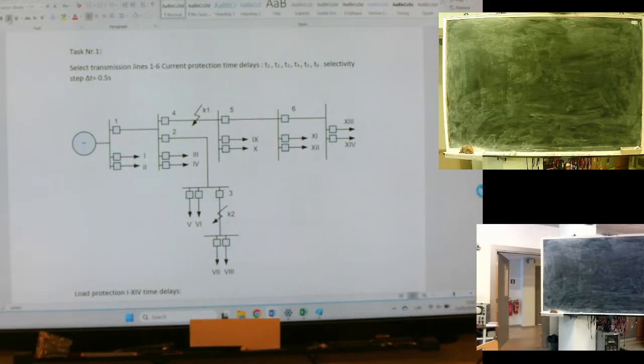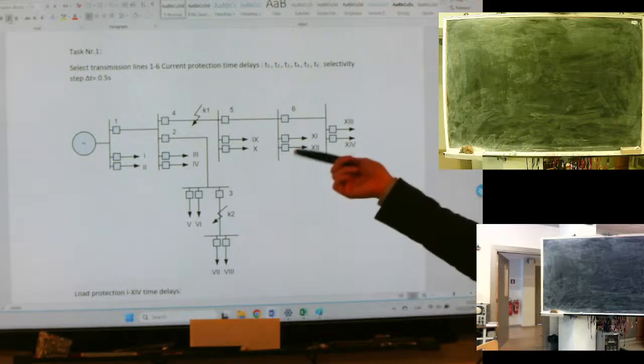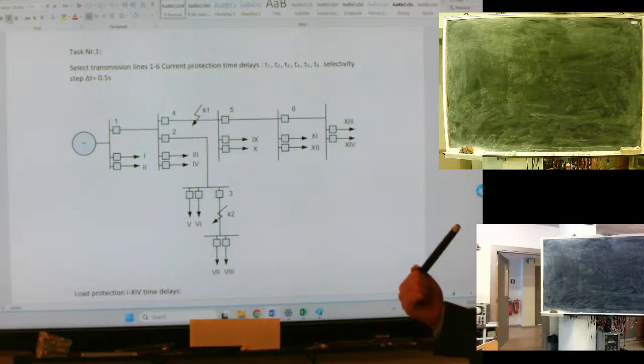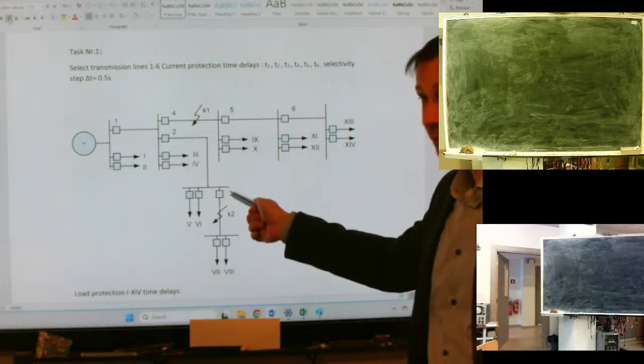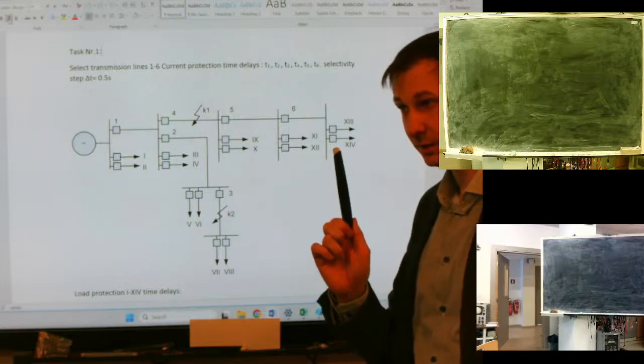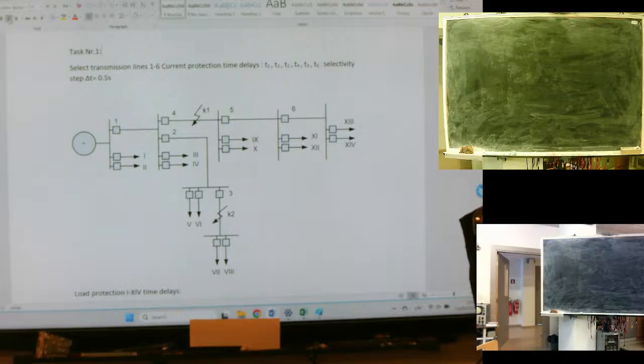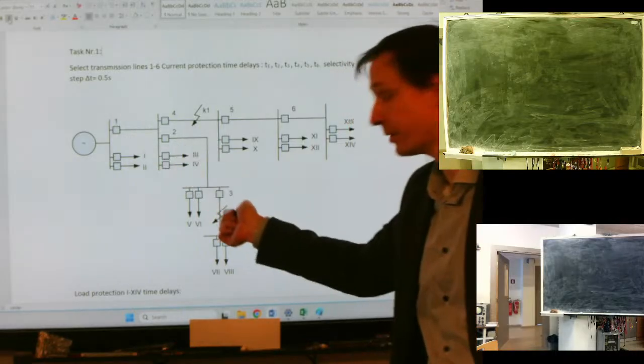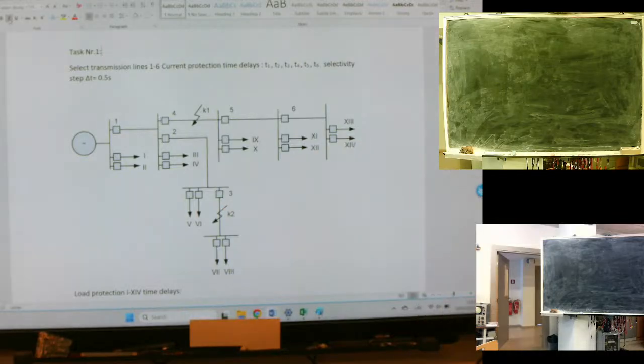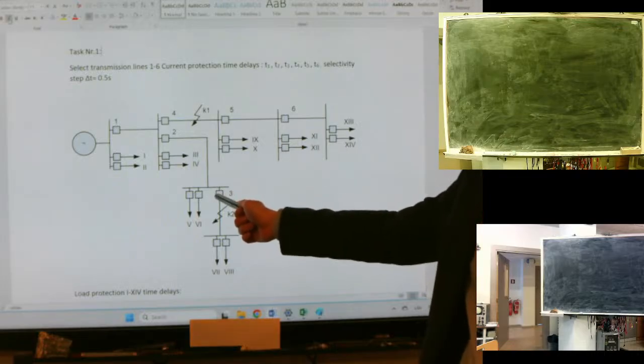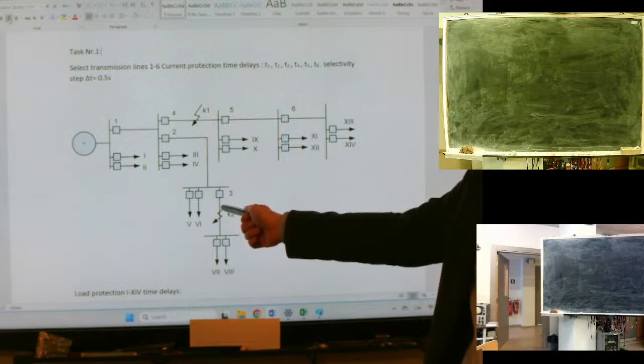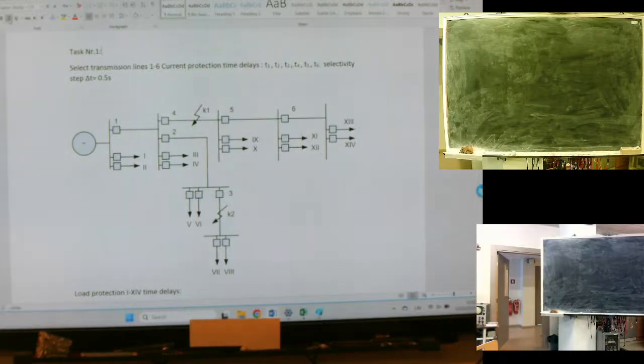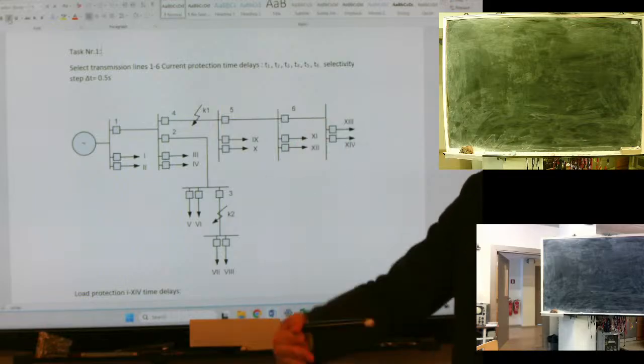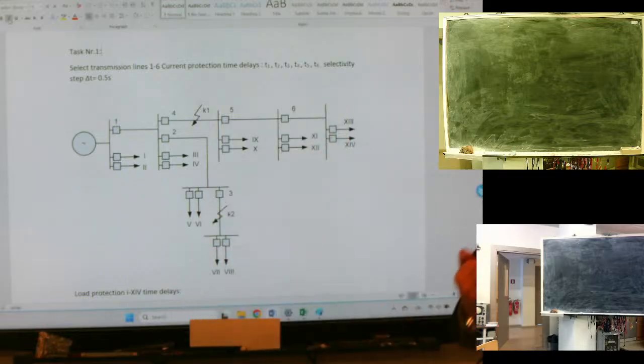That's why when we design this, because this is a very simple overcurrent protection design, we make it so that all current protection in series could detect. So we calculate and select such a current protection set point for detection that all protection in series could detect this fault. But we want the current protection number 3 to operate first. How could we make it? Using time delay, the main tool for selectivity. To make this sequence, who will be the first, the second, the third, and so on, is the possibility to use time delay for operation.